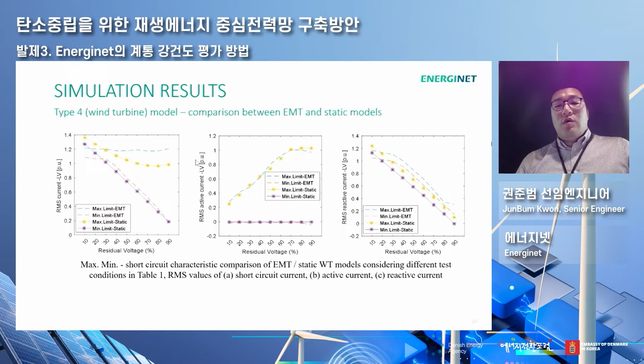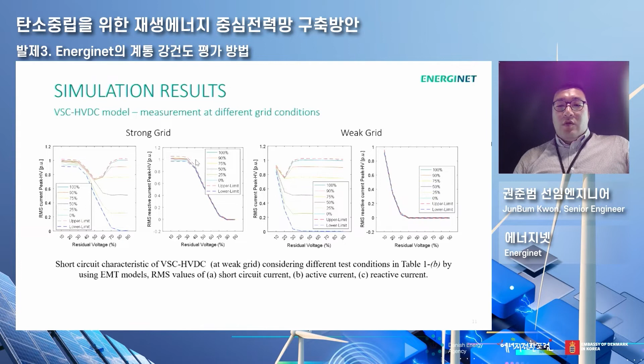So, the maximum and minimum short circuit characteristic comparison of EMT and static WT model, considering different test conditions in table 1: RMS value of A, short circuit current, B, active current, C, reactive current. You can see that they really coincide. So for existing wind farms or PV or other things, through internal tests using the EMT model, we can see exactly what the contribution to the short circuit is. So we evaluate, all the data are input as RMS values, and then we conduct the calculation.